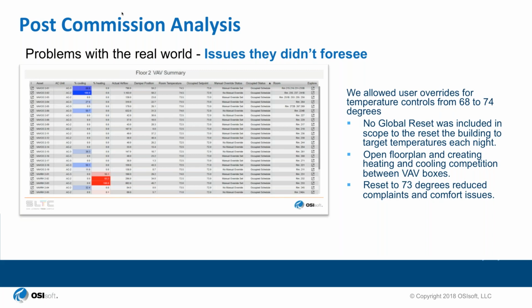Second, they implemented no global reset. So when a person changed the thermostat, it stayed that thermostat during occupancy from now until someone else changed that thermostat. So the building could never get back to its own design standard.